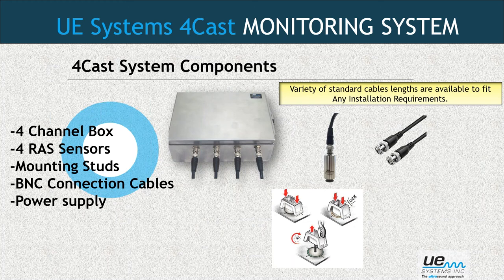Let's take a look at what the 4Cast components are, or what the system consists of. First, we've got a 4-channel box, stainless steel, about 5 inches by 4 inches by 2.5 inches thick. You've got 4 of our RAS sensors, the exact same RAS sensor used with handheld ultraprobe devices. So if you've currently got routes set up in your plant with RAS sensors mounted, taking monthly readings, maybe due to access issues or safety concerns, you could seamlessly unplug the BNC and plug it right into the box.